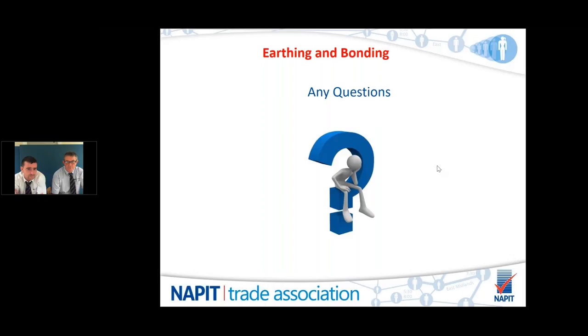Thank you both. So we've got a question that's come up a couple of times from both Daniel and Andrew, and it's about, can you shed some light on the main protective bonding of plastic, gas or water pipes into domestic installations? So specifically new builds are experiencing this at the moment. So the one I'm doing at the moment is fed via a plastic pipe, which then continues in plastic pipework for a large proportion of the property.